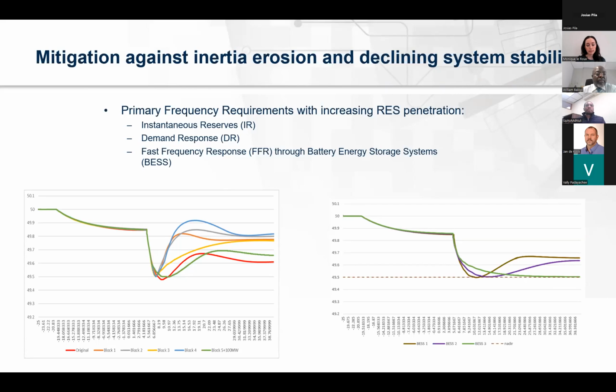And then the graph on the left was where we tripped some of the load blocks on the system, and then you can see exactly how your system frequency is going to respond. The blue line just shows a bit of an overshoot in the frequency, so then you know exactly how much load you need to trip or how much you need to keep online so that you can keep your frequency stable. And then on the right hand side, we introduced some battery energy storage onto the system, which provides very good fast frequency response and can respond to any frequency changes quite well. So as you can see, you want a stable system, and there are quite a few things that we can do going forward, for instance battery energy storage. There are other measures like synchronous condensers, etc., that you can also introduce into your system to keep it stable and keep it in an operating space where it's easy to operate your system. Okay, I think that was my last slide.